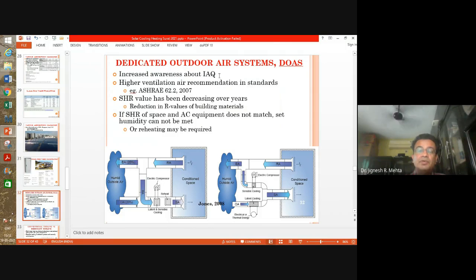So you might know that nowadays there is more and more discussion about indoor air quality, right? In this scenario of pandemic also, you're talking about better ventilation, that is providing more and more outside air or fresh air, so that the concentration of pollutants generated indoors does not go high. So when you put more outside air in an air conditioned area, it carries higher, not just sensible load, but also latent load. So a dedicated outdoor air system may become relevant in this case.